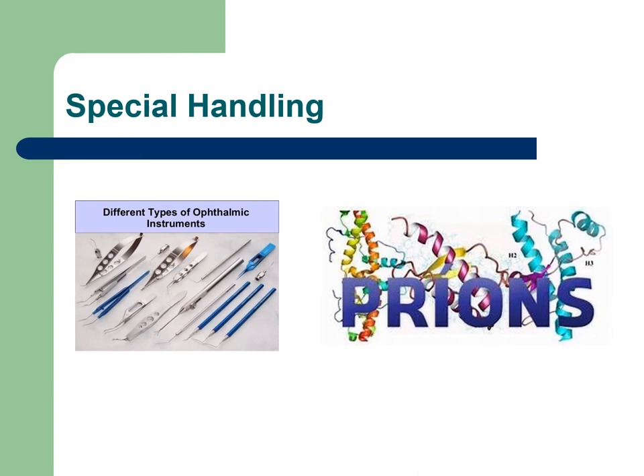But now the Society for Healthcare Epidemiology of America, SHEA, says there are four ways to reprocess these instruments. The first is steam sterilization at 273 degrees for one entire hour. Usually we expose instruments for about 4 minutes, so 4 minutes compared to an hour is a long cook time.